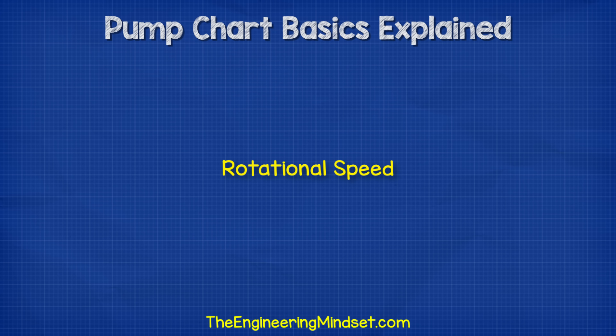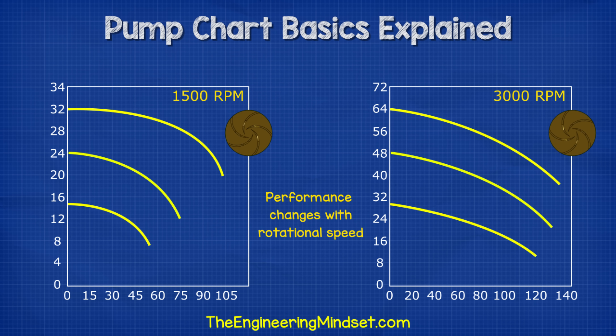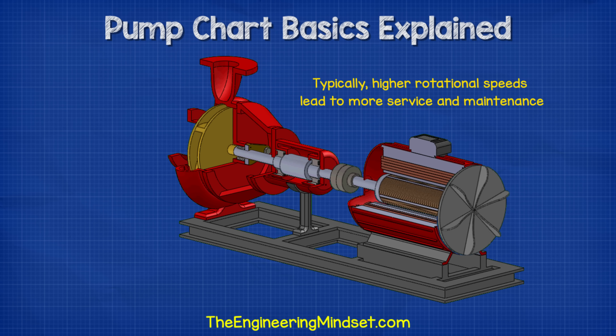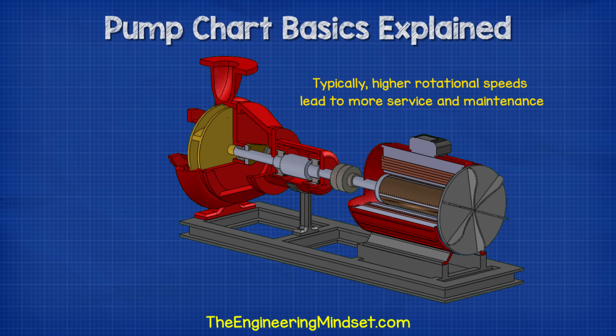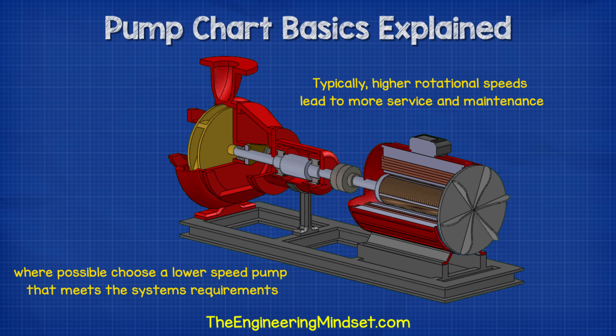Rotational speed. Some pump manufacturers will provide separate charts for operating the pump at different rotational speeds. We can then compare the performance to get a close match and then find an electrical motor which will suit our needs. Typically speaking, higher rotational speeds lead to more service and maintenance, so where possible, it's good practice to choose a lower speed pump that meets our system requirements.